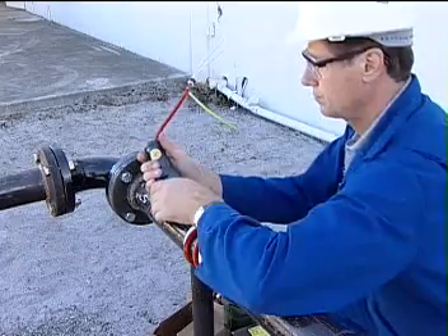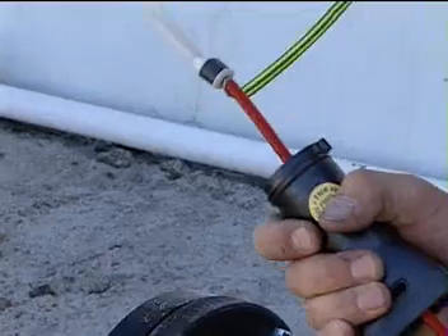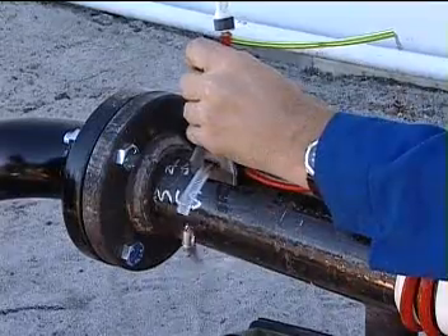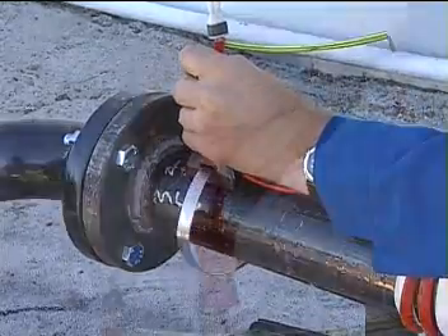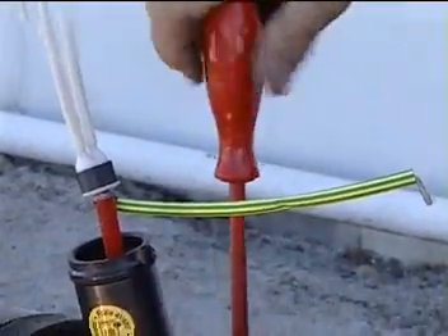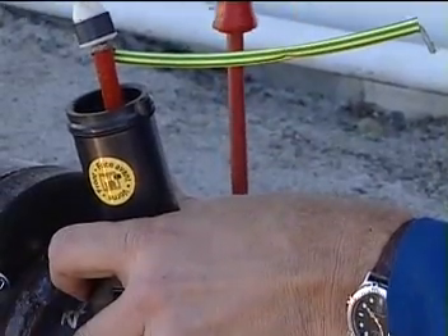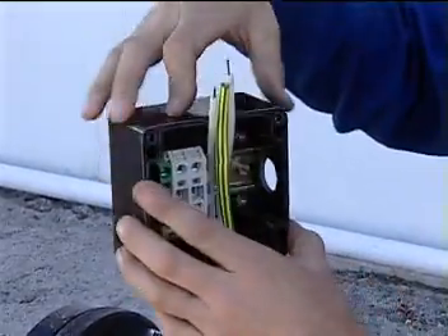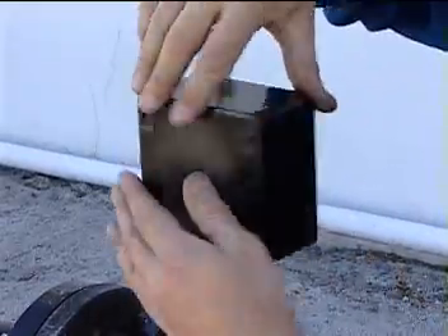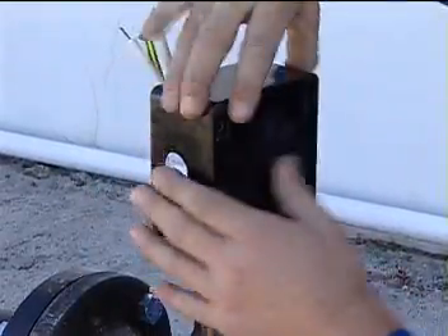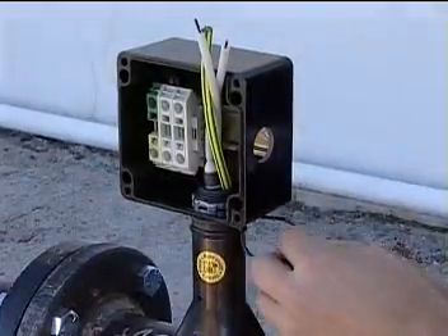Pull the heating cable back into the stand so that 1 inch of the cable is exposed. When fastening the stand to the pipe, use the appropriate number of straps indicated in the installation instructions. Be careful to run the pipe strap under the heating cable. Be sure to tighten the boxes completely onto the stand so that the grommet seals properly. Install the cable ties so the box will not rotate.